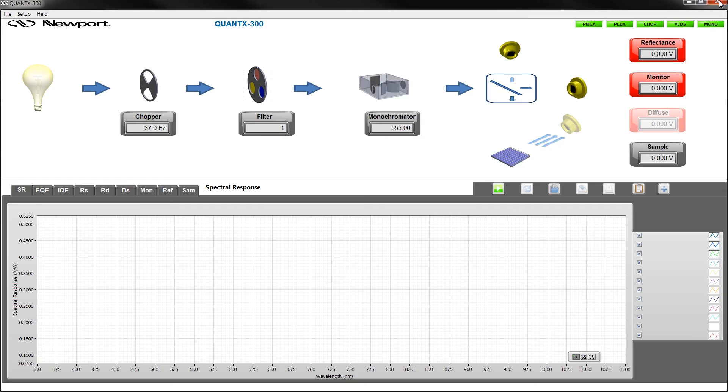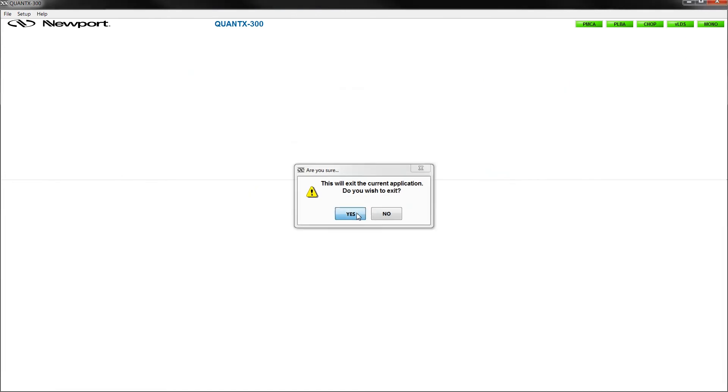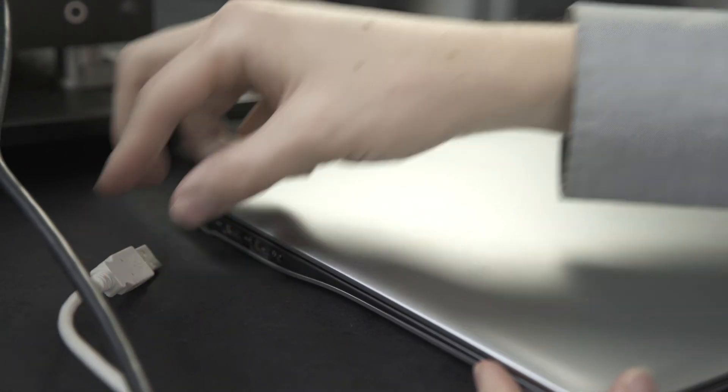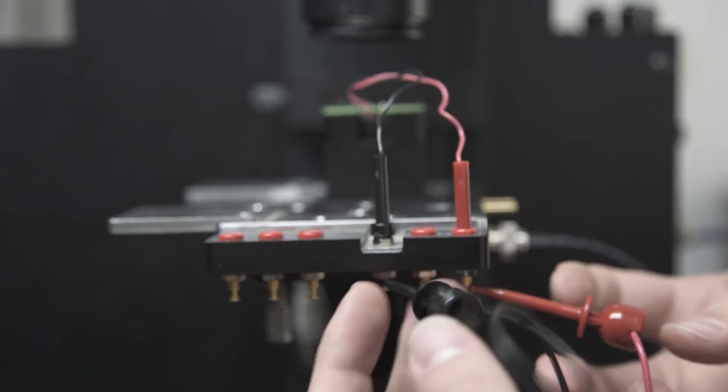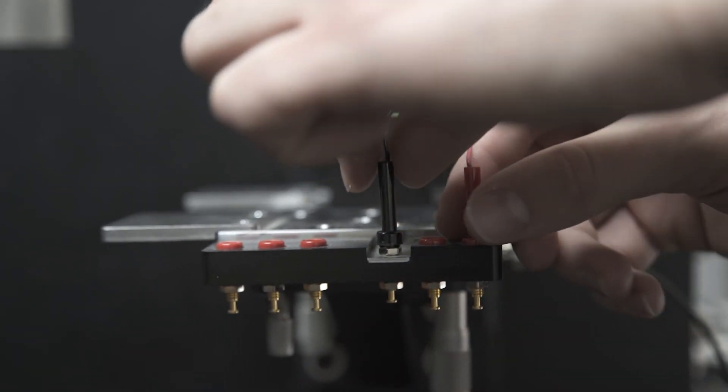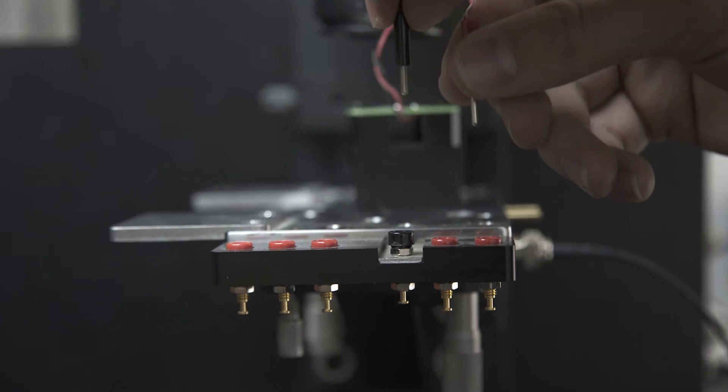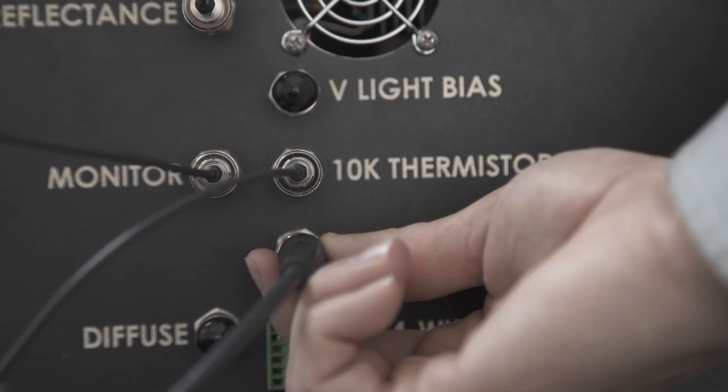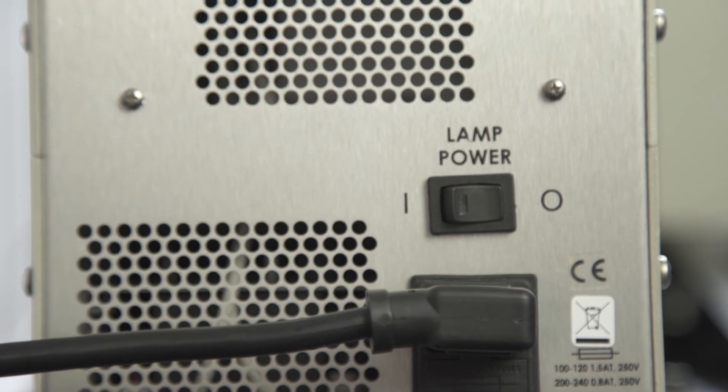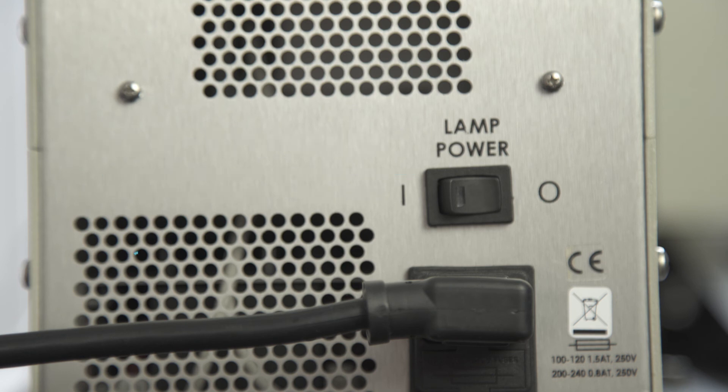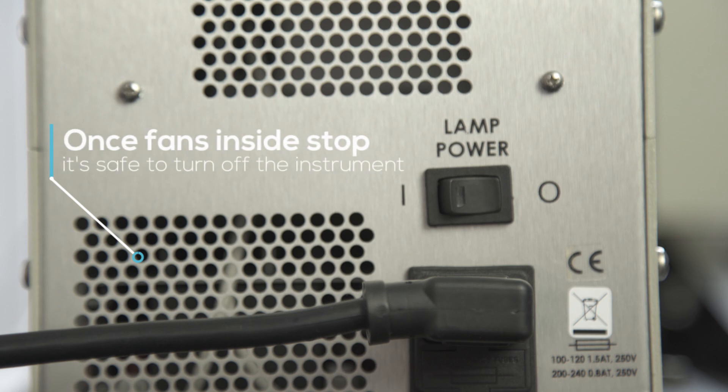When you're ready to shut down the system, the first thing to do is exit the software by clicking the red X in the top right corner of the program. The laptop can now be powered down and the USB cable disconnected. Disconnect the sample or reference standard under test. Turn off the light source by flipping the switch to zero. It's important to wait approximately five to ten minutes for the lamp housing to cool down before shutting off the main system. Once the fans inside the housing stop, this is a clear indication that it's safe to do so.